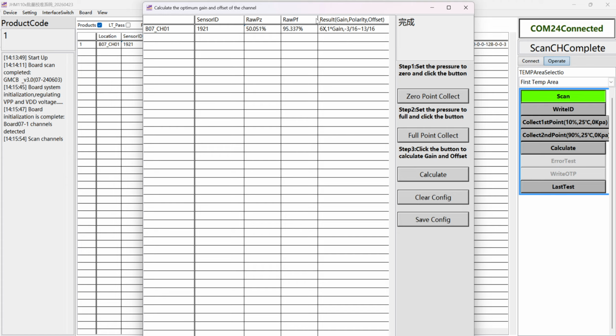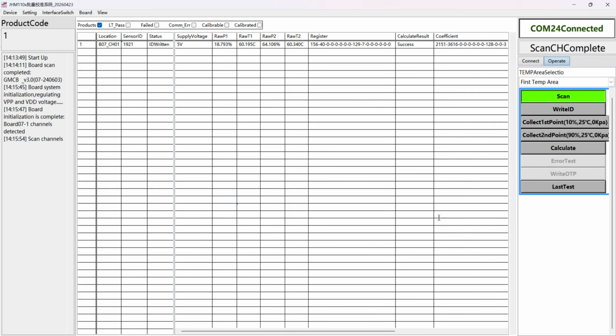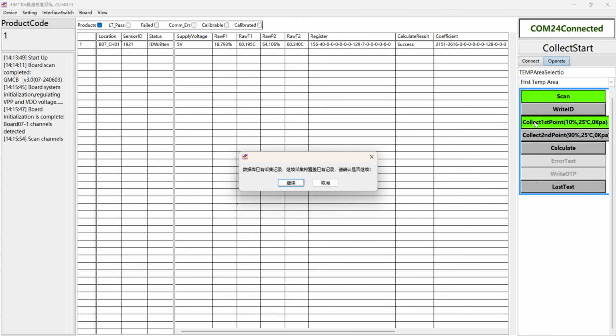Then I will do the calculation. Calculating is finished. Here the gain, polarity and offset are collected here, because I have already operated it before, so this data is the same as I have done before. And then I will save this configuration. Okay, I have saved it, and then I will change this rotary to the 0 point, and I will collect the first point. It's 10%, double click. I have already operated before, so it shows that some data already existed, and when I overwrite this data, I will continue.